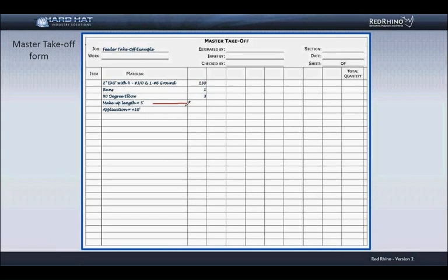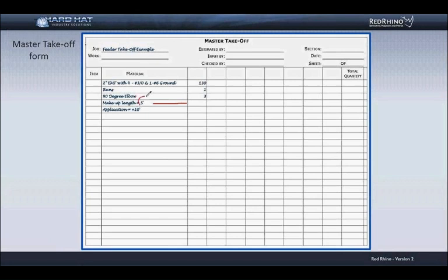The wire makeup length needed for the 225 amp panel I estimate would be around 7 feet. 7 at one end plus 3 at the other end is a total of 10 feet. 10 feet divided by 2 calculates the makeup length to be 5 feet. I'll demonstrate how wire makeup is entered in Red Rhino in a moment.